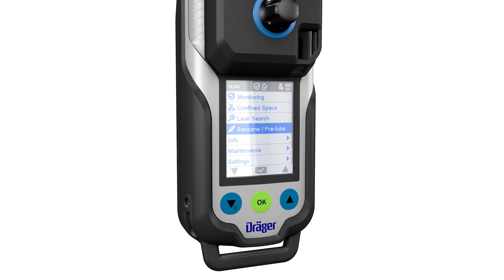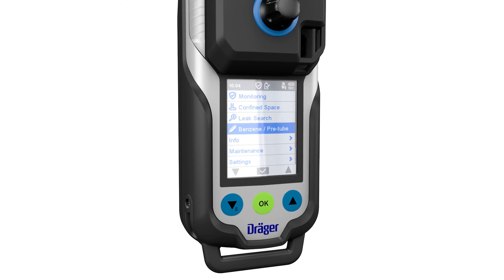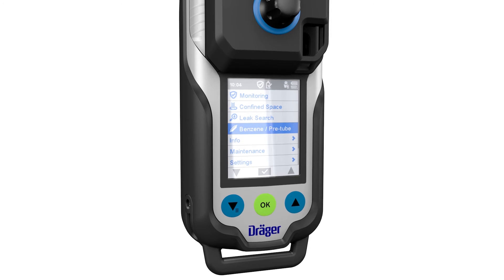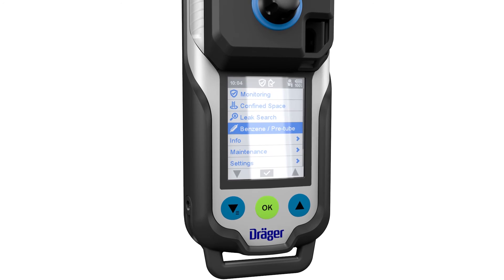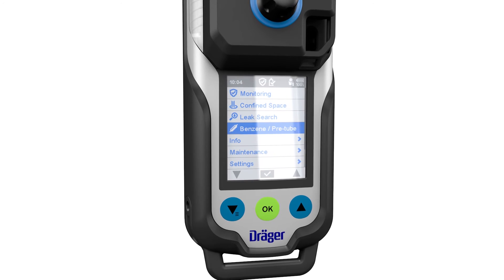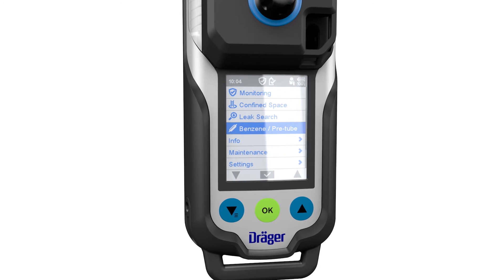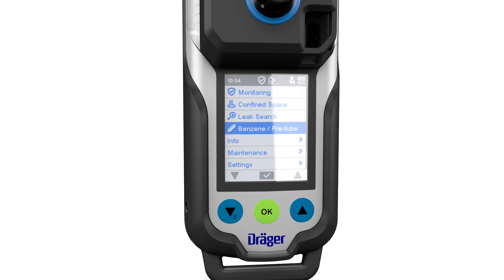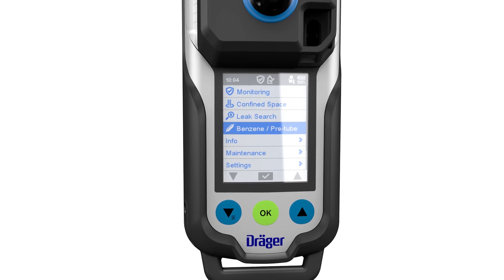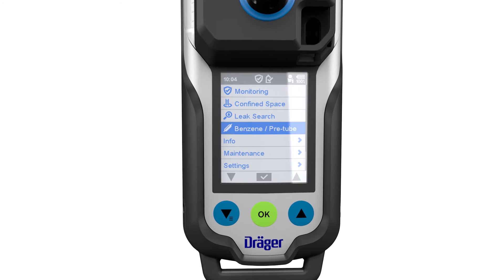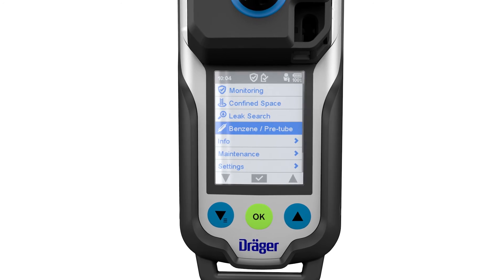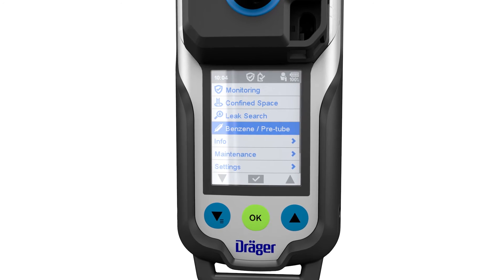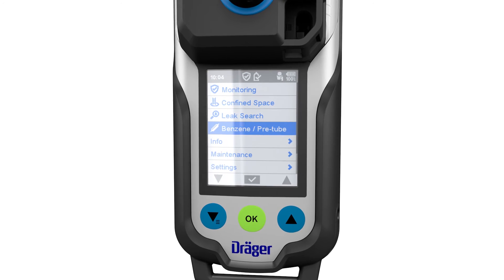During PID pre-tube measurement, the visual, audible, and vibration alarms and the alarm evaluation function are deactivated. At the same time, the target gas and the peak values are shown on the display. None of the other sensors are active.